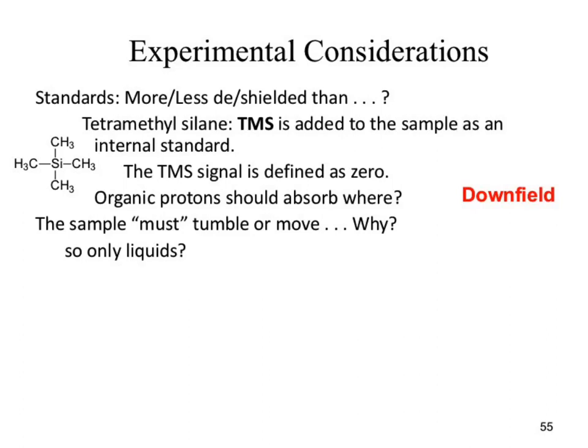Okay? So this means we can only run liquids because it has to move. So I wouldn't be able to test a solid. Right? Well, that would suck. How do I get the solid to become a liquid? I'd have to heat it up, but then that could potentially run into thermal issues with the magnet. So how else could we test the solid? Put it in a solution to get a liquid.